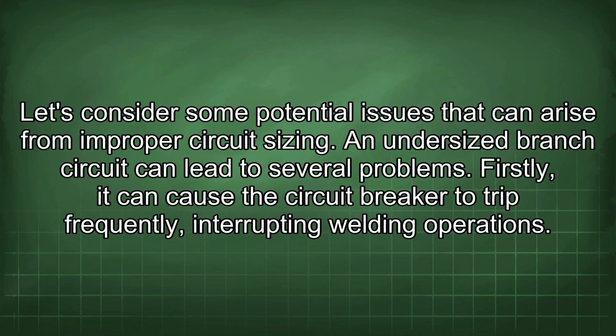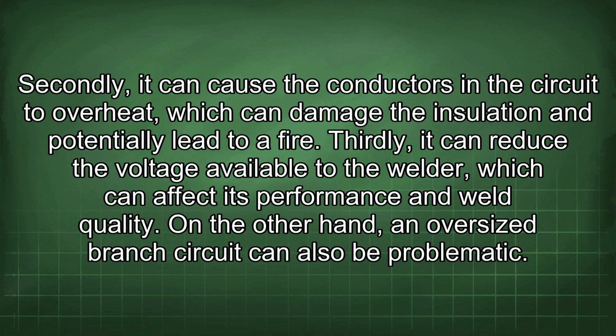Let's consider some potential issues that can arise from improper circuit sizing. An undersized branch circuit can lead to several problems. Firstly, it can cause the circuit breaker to trip frequently, interrupting welding operations. Secondly, it can cause the conductors in the circuit to overheat, which can damage the insulation and potentially lead to a fire. Thirdly, it can reduce the voltage available to the welder, which can affect its performance and weld quality.